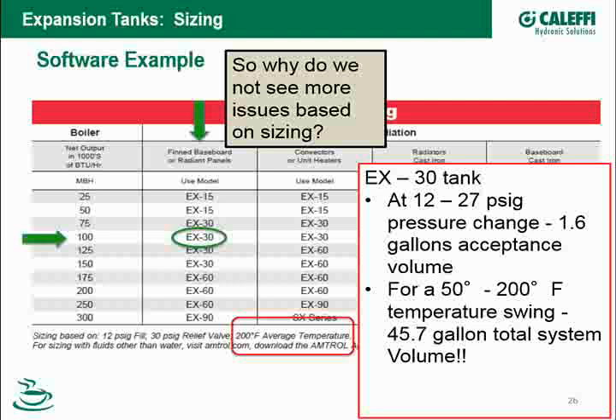Hey, Jody, if I could add one thing in here. I know there's a lot of guys, one of the websites that I hang out on is guys that do wood and pellet boilers, and oftentimes they'll have a lot of storage capacity with them, sometimes hundreds, sometimes thousands of gallons. Some guys got 1,000, 2,000 gallon LP tanks in for storage. So something like that, you have to be careful when you have that kind of volume, and really crunch the numbers, because with a 100,000 BTU boiler and 1,000 gallons of system capacity, this obviously wouldn't work.